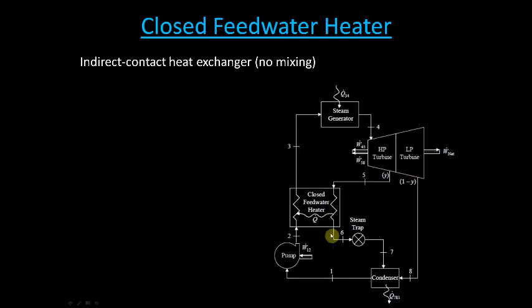Okay, and you see this a lot of times. Closed feed water heaters are often used in steam plants when they're trying to heat the actual water that you're going to use, because the water that comes out of your shower or your sink is not going to be the water that went through the steam plant. You're not going to have that mixed in because it's gone through all those pipes and through the turbines and so on. But what you're going to do is have that heated water run next to a pipe that would go to heat the water you would use in your building. That's kind of how a closed system heat exchanger would work.